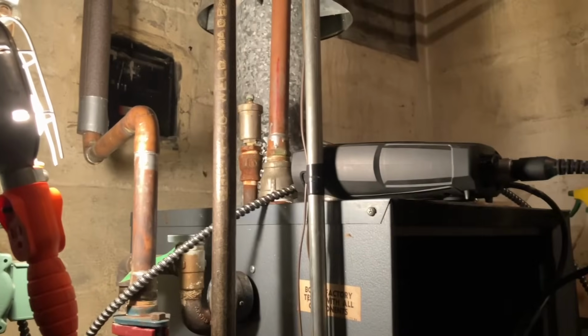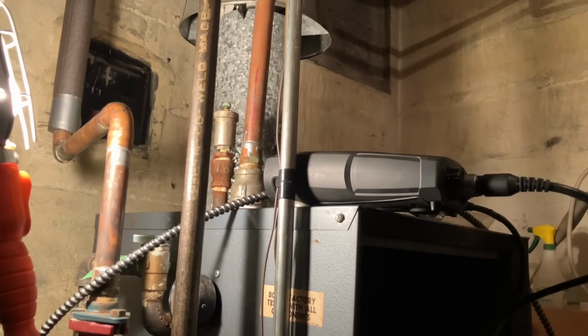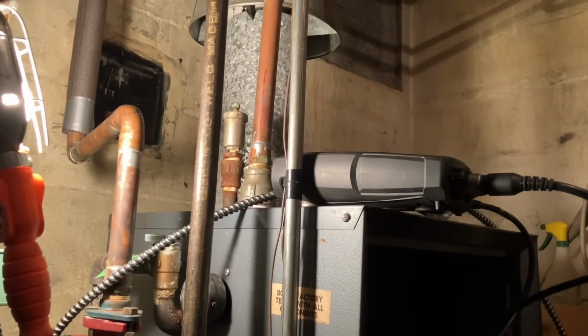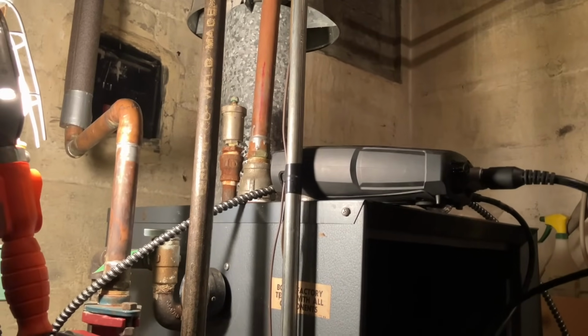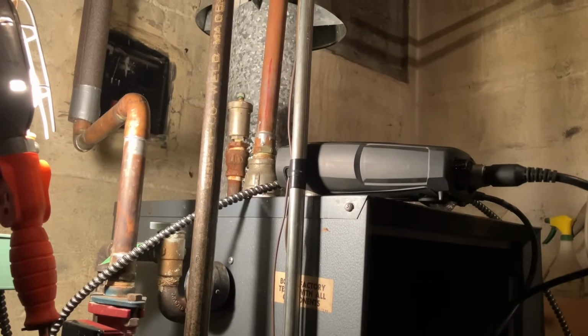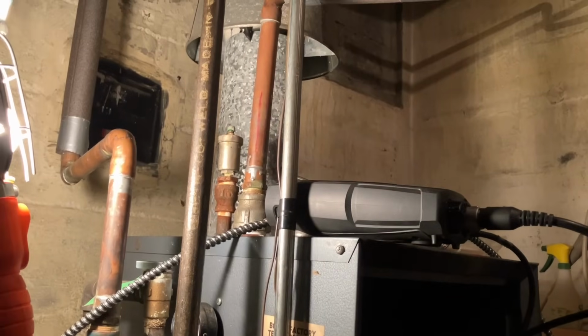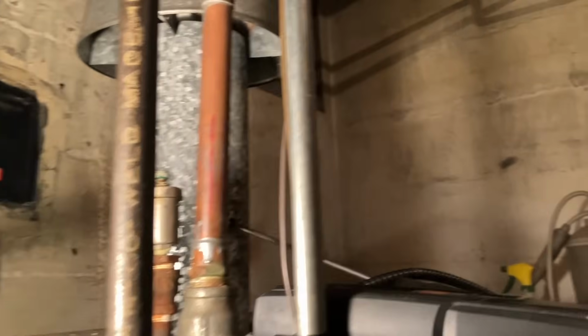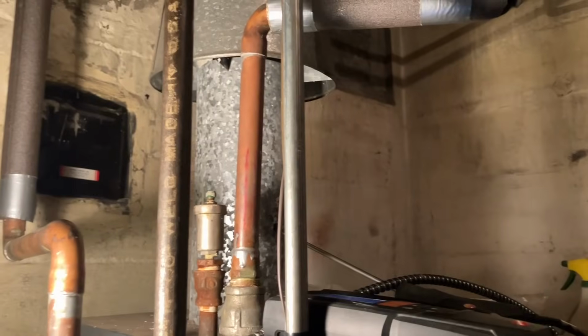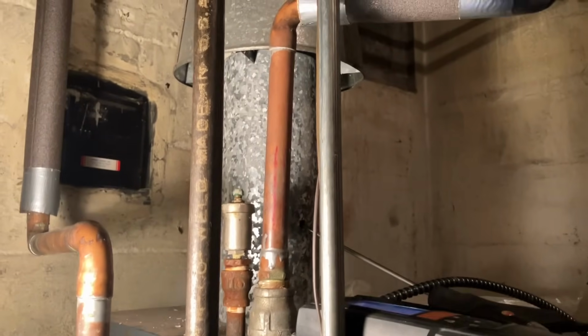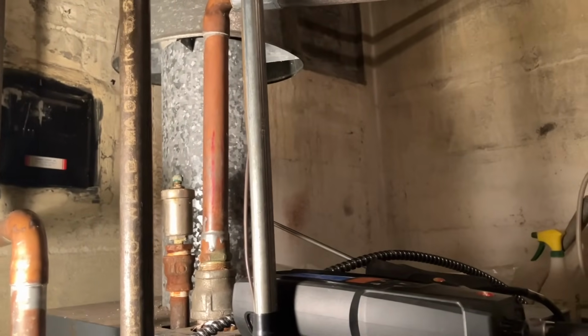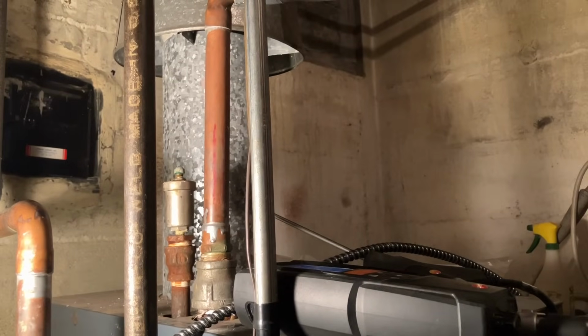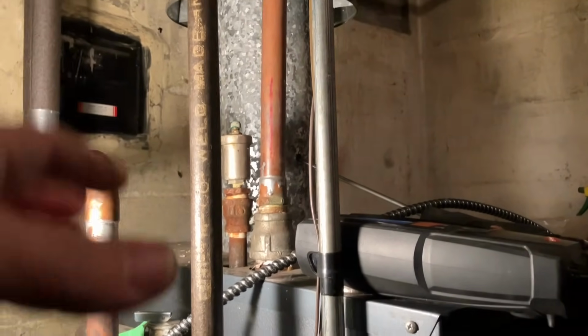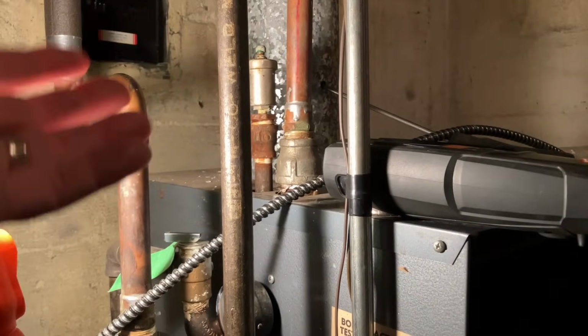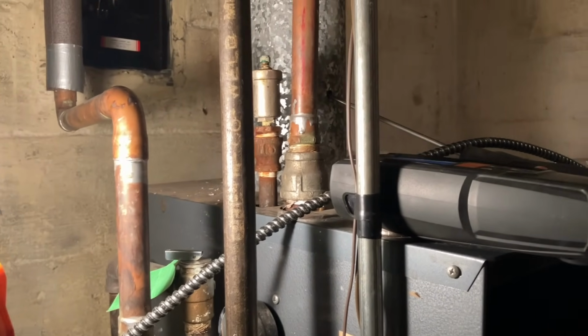That's the condensate you capture, because the last guy said to me, I've got to put in a condensate. No. On high efficiency equipment, where you have condensing boilers, you will have condensation as a byproduct of combustion, immediately at the source of creation at the boiler itself. Oh, right, gotcha. Also, when it discharges out of the house in a PVC or polypropylene pipe, it's already condensing, so that's why it pitches outside sometimes, or pitches back to the boiler so it can go into a drain, like a condensate neutralizer pump, for safe discharge of that condensate.